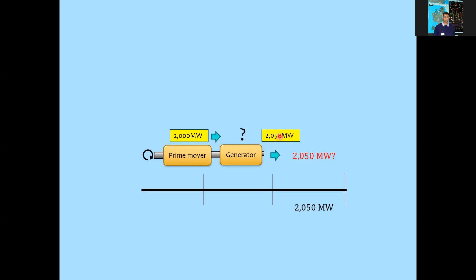Now, how is this possible? This is where a very important concept comes in, called kinetic energy. What is happening is, even though the prime mover is not supplying the generator with this balance 50 megawatts, the stored kinetic energy in all the rotating parts of the system is getting converted to electricity during these supply-demand imbalances. So it is the kinetic energy that supplies the shortfall, balancing it until the prime mover increases output, so the generator can still provide the additional 50 megawatts the consumers are demanding.